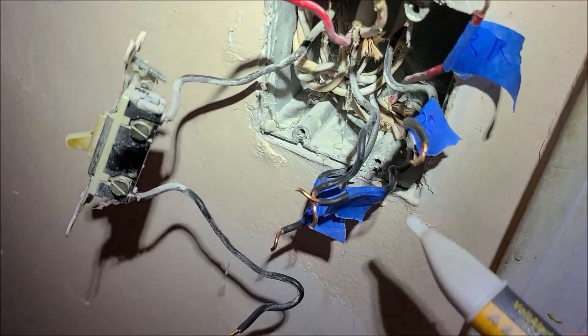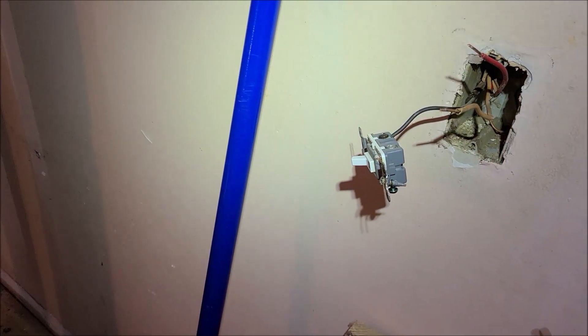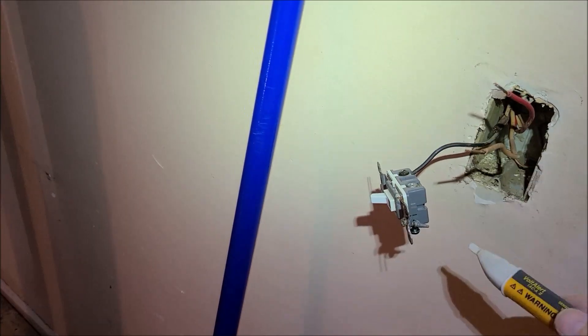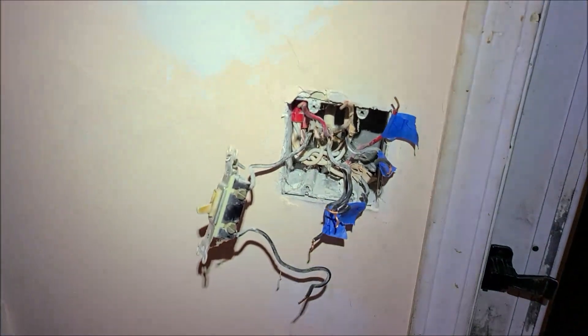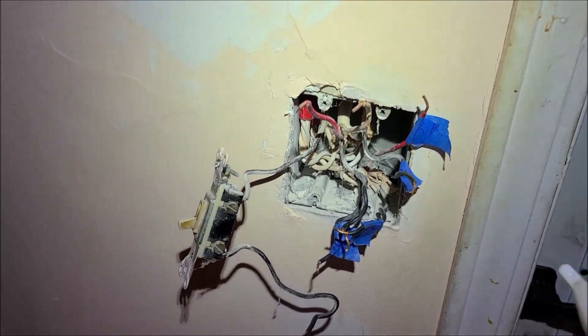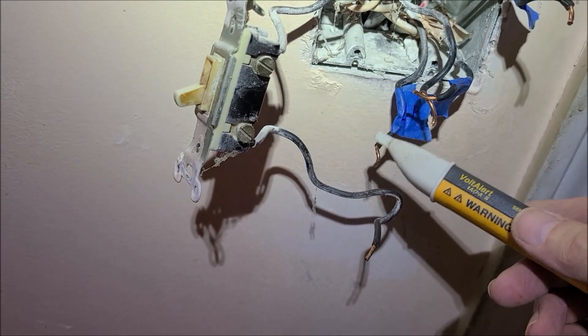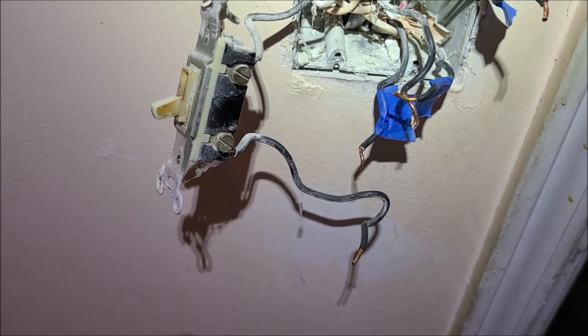While I'm under here with the cave crickets - I found the wire, it's dead, that was the original wire that went to the front yard. But someone's left a cluster of wire down here. There's a hole just below the light switch by the front door - and here it looks a little scary, see all that burnt, melted, maybe corrosion. We're outside - we found the wire, it's hot, so I'll go label it. It goes through the yard out that way to the light pole. Now for our last wire - I'm sending 120 volts out and I assume it's going to go over to the other three-way switch - and it does. Everything's labeled. I'm wondering though if this light pole wire could be shorted out underground, causing some back-feeding weird issues.